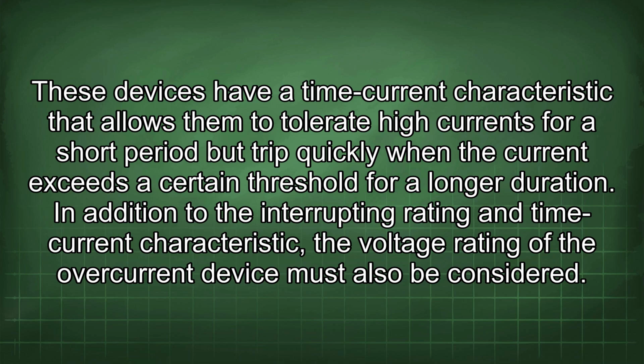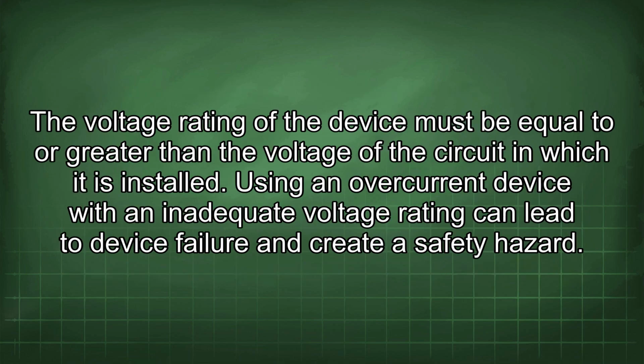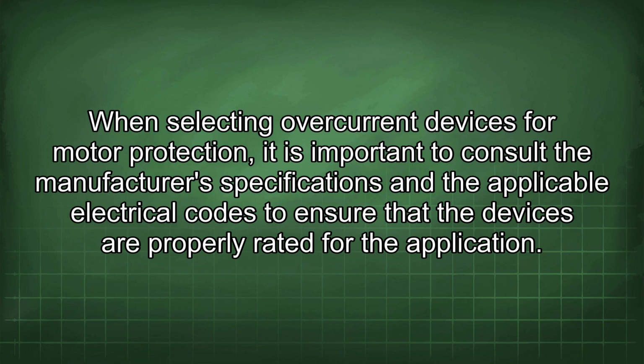In addition to the interrupting rating and time current characteristic, the voltage rating of the overcurrent device must also be considered. The voltage rating of the device must be equal to or greater than the voltage of the circuit in which it is installed. Using an overcurrent device with an inadequate voltage rating can lead to device failure and create a safety hazard. When selecting overcurrent devices for motor protection, it is important to consult the manufacturer's specifications and the applicable electrical codes to ensure that the devices are properly rated for the application.